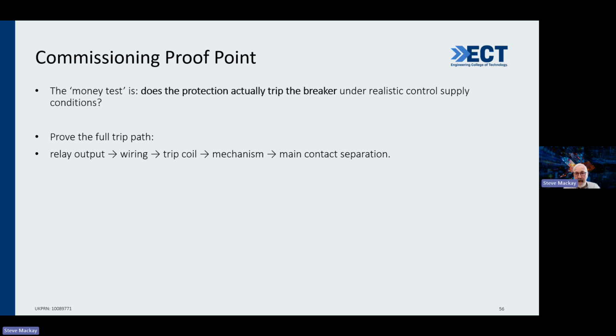What happens? I must say, in industrial automation, you always have a thing called fail safe with process control stuff. In other words, no power, you protect. But what happens when you've got a breaker with a trip coil and there's no DC power for it? What happens then? Do you have fail safe then?